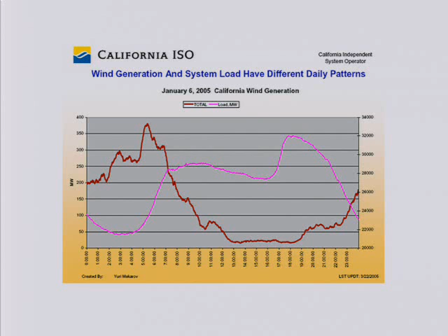An even greater concern is looking at a finer time scale. What worries system operators isn't just the macro level, when does the wind tend to blow and when doesn't it, but the rapidity with which it picks up and drops off. It's the slope of this wind output line that's really a concern, especially when you have steep ramp rates. What happens if that coincides with electric demand picking up while the wind drops off? Then you have a steep ramp rate in megawatts per minute or even per second, that the system operator is responsible for balancing. The power system as we know it hasn't really been equipped with the capability to do that.